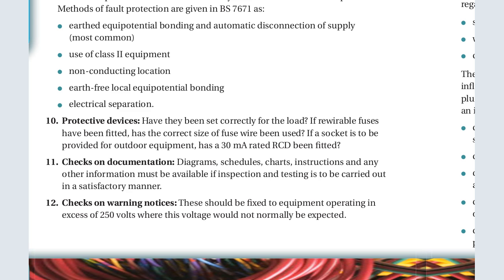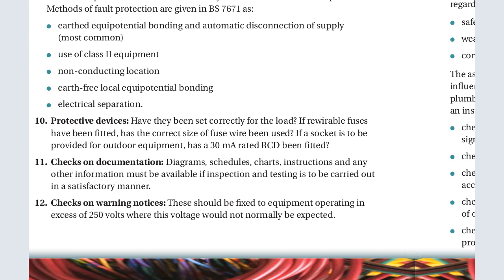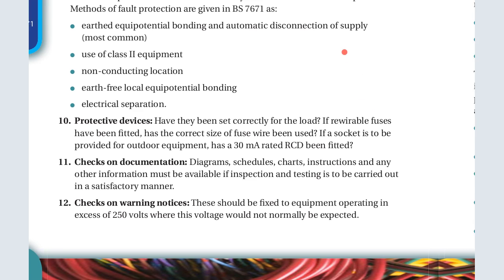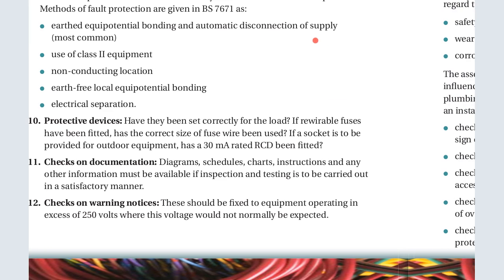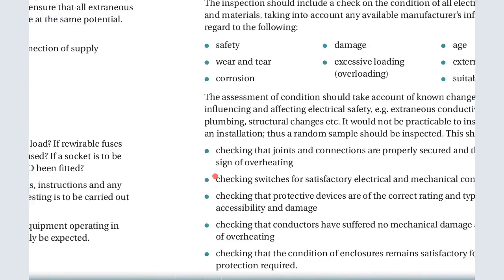the documentation. We look at the diagrams. We also keep in mind that anytime we have an installation, we normally have wiring diagrams, schedules, charts, and instructions, and any other information must be available if inspection and testing is to be carried out in a satisfactory manner. Also check the warning notices. These should be fixed to equipment operating in excess of 250 volts, where this voltage would not normally be expected.